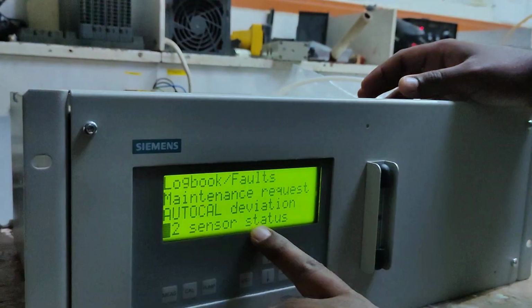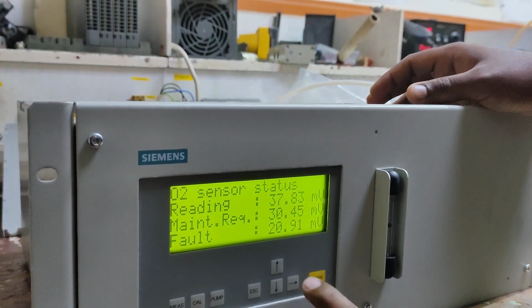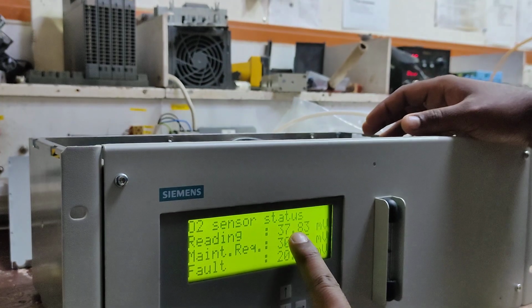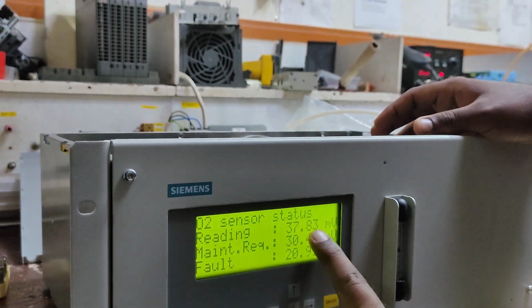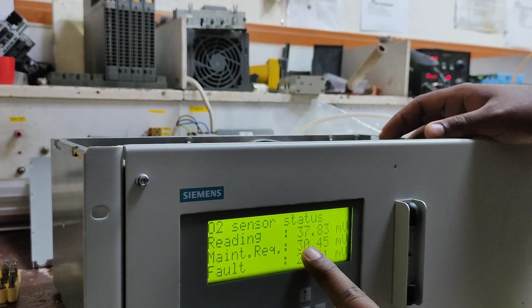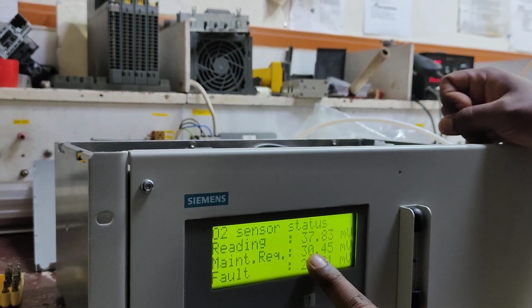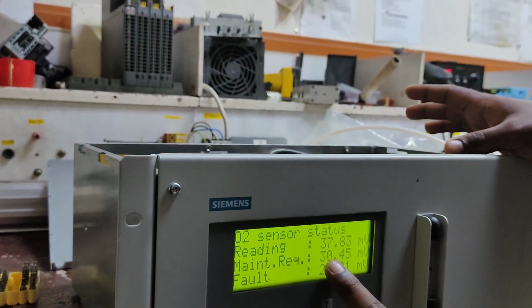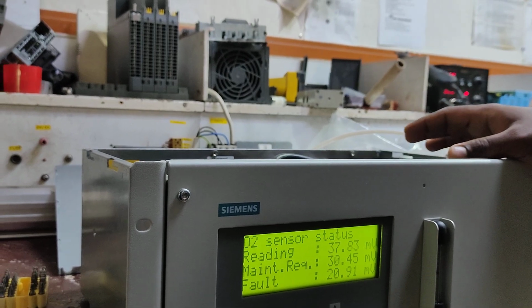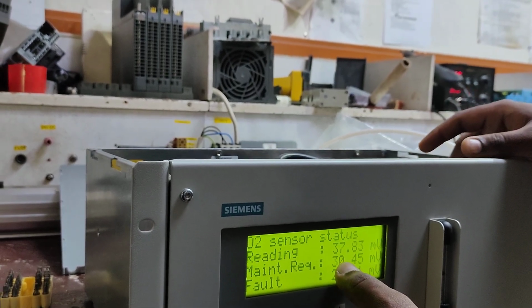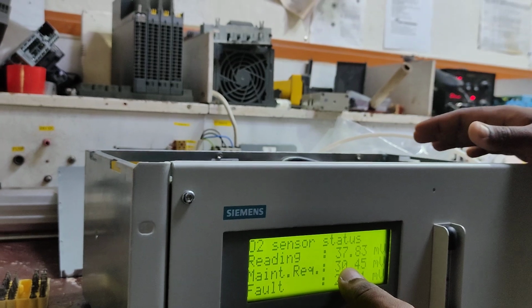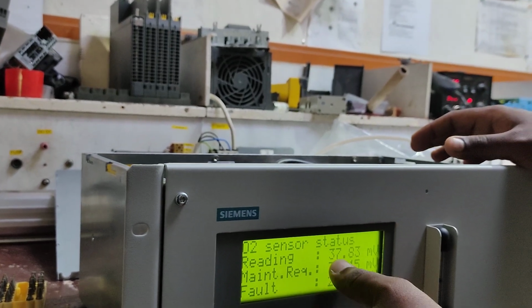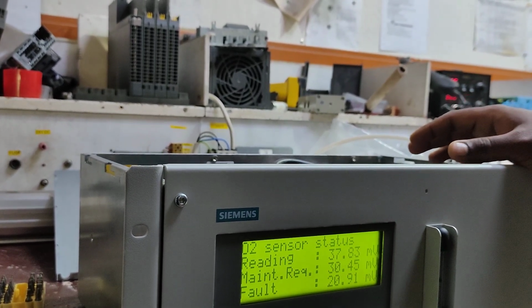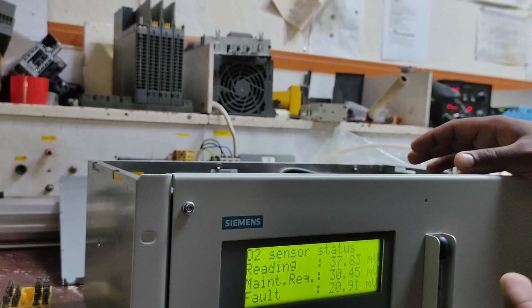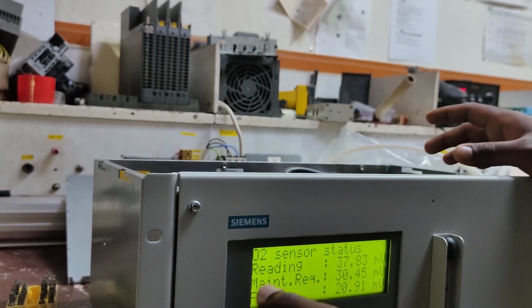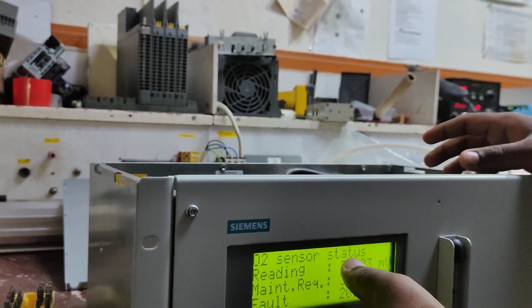Then this is the O2 sensor status. What is the status of the O2 sensor? You are presently measuring 37.83. When it reaches 30 millivolts, at that time it will give you an alarm, like a maintenance request. By 20 it will be a fault. So when it reaches 30, you have to look for replacement of the sensor. Between 30 and 20 you have that 10 millivolt period where you can replace the sensor. Usually it will be around 37.87.